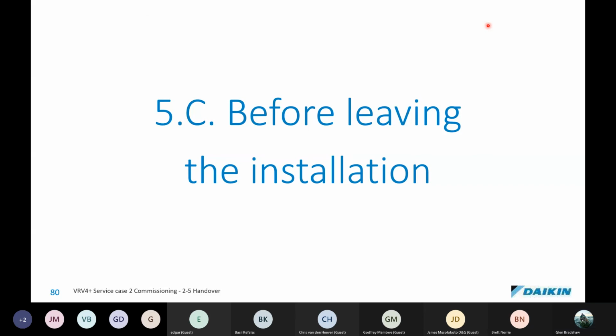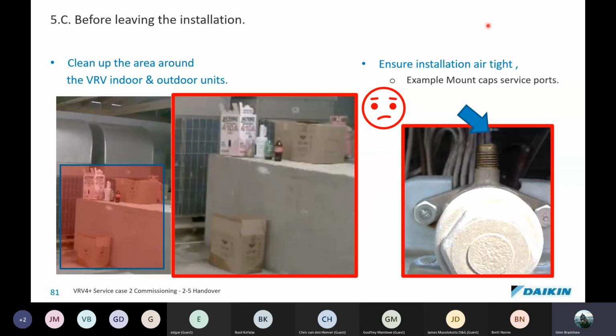And then before leaving the installation, clean up. There's nothing more exciting than to arrive on a site that's had a brand new air conditioning system installed, and lying everywhere are empty cans of refrigerant, vacuum pump oil canisters, Coke bottles, cigarette stompies. And the one thing that really drives us mad is when the caps are not placed on the service valves. Schrader valves need to be capped to stop them from leaking. There's always a small amount of refrigerant leaking from them, and over a period of time, this will have a negative effect on the system.